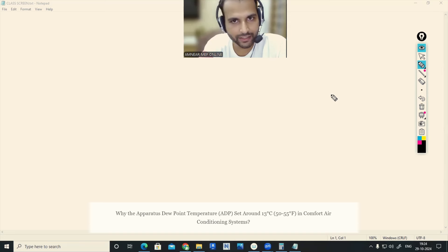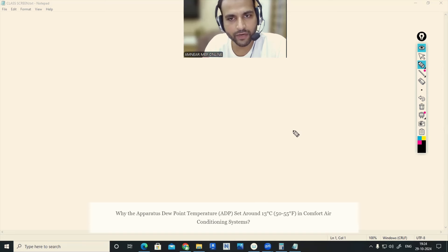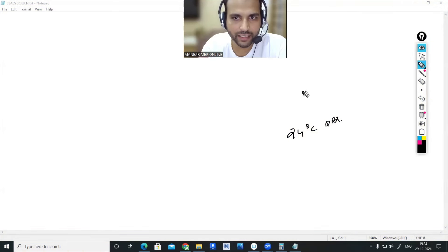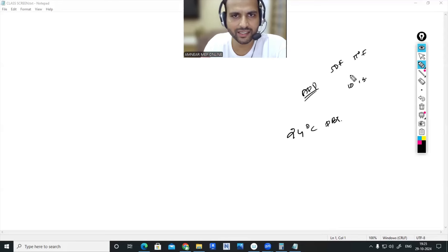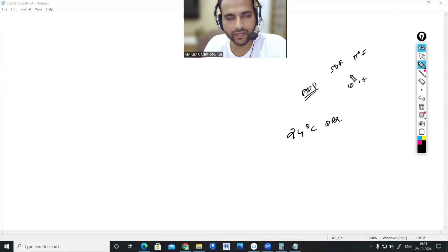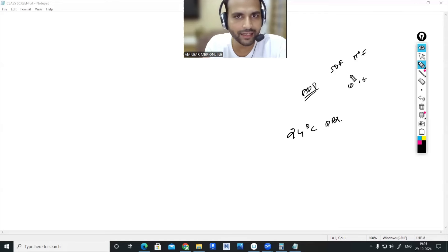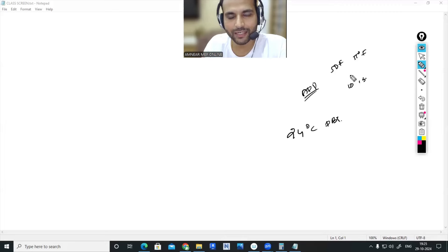A lot of guys might be having this doubt that I am going to explain. Even if the room temperature requirement is 24 degrees Celsius dry bulb temperature, sometimes the surface temperature of the cooling coil — the apparatus dew point temperature — especially in comfort air conditioning systems, is near to 13 degrees Celsius, or 50 to 55 degrees Fahrenheit, or somewhere between 10 to 13 degrees Celsius. Why is that? What is the reason behind it? Because our room temperature is 24, then why do we need to keep the surface temperature of the cooling coil nearly 10 to 11 degrees less than the room requirement? Experienced professionals might already have the idea, but still a lot of guys have this doubt, so let me explain.